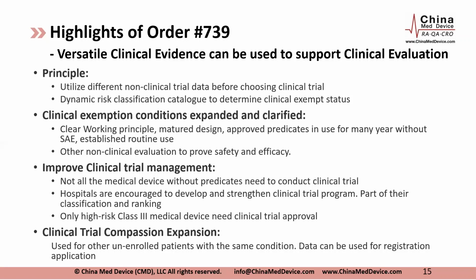Clinical trial exempt means you still have to do a clinical evaluation, because if you look at the hierarchy of the effort, the best thing is you don't have to do anything. You just summarize your technical and clinical justification. If you're on the clinical trial exempt catalog in the old days, you still had to really try hard to work on clinical evaluation. There's the simple clinical evaluation, there's the complex one, depending on how much evidence you have. Now it's called the clinical evaluation. I'll talk more in a few slides down, but at least it's more dynamic. It's not clear-cut black and white anymore.